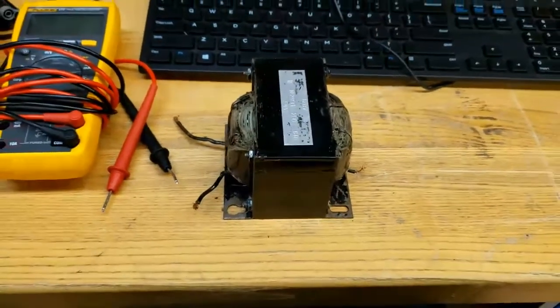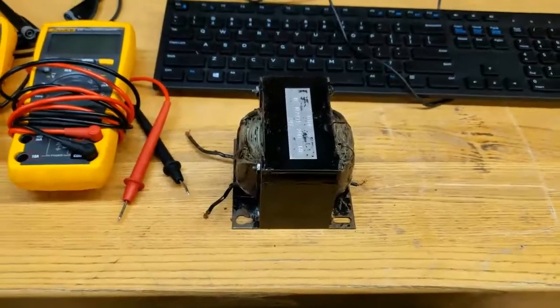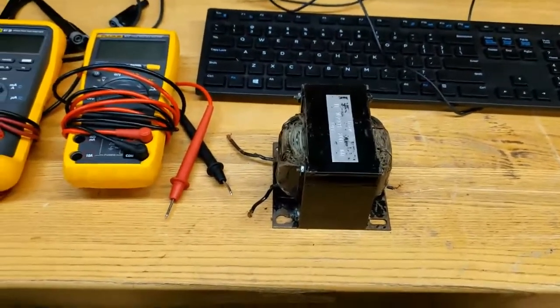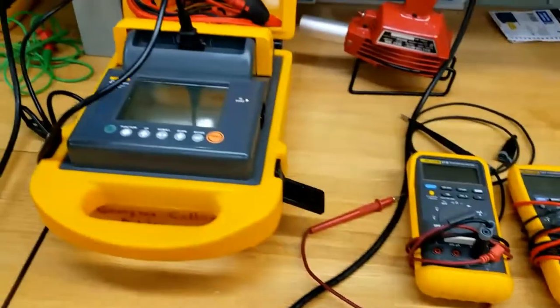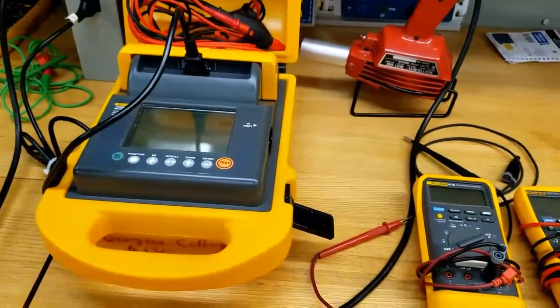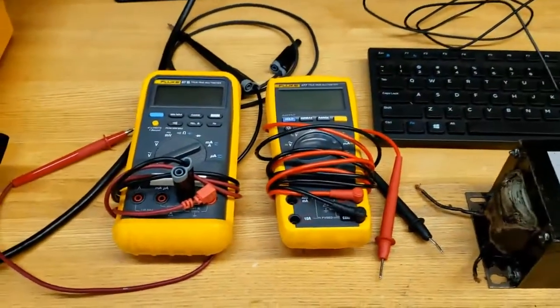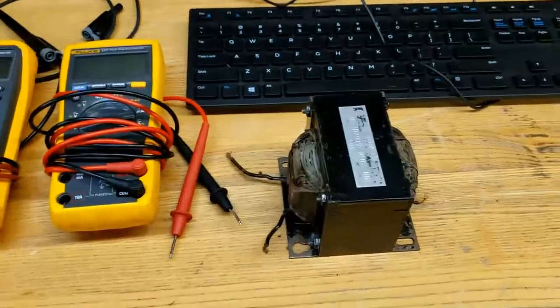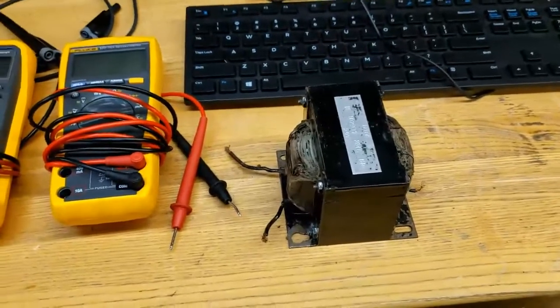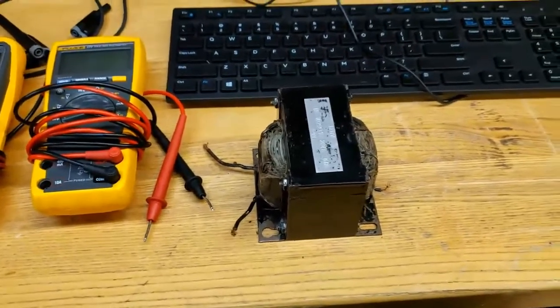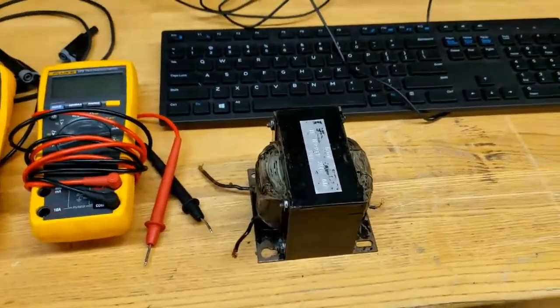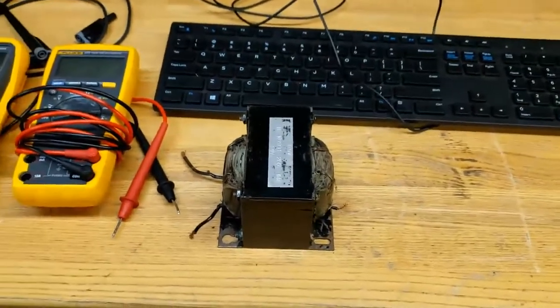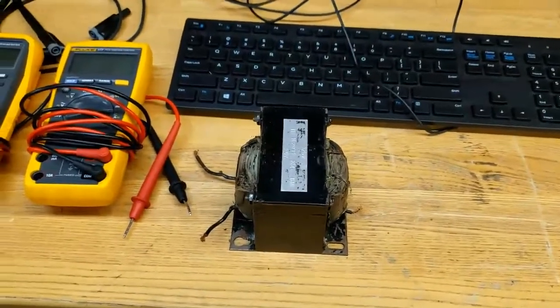The basic steps of this lab are: you're going to test this transformer dry, megger it out, high to ground, low to ground, high to low sides. Take a DMM and measure the resistance of both windings, primary and secondary. Then call me. I will wet the transformer. This is to simulate a flooded basement room with a transformer.